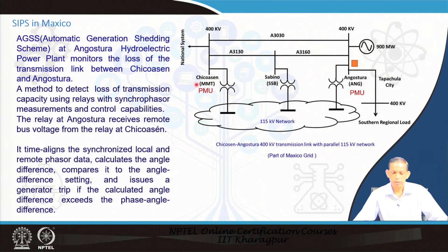So, what is being done here is that the double line outage produces a 14 degree angle between these two sides, and one line outage provides around 7 degrees of angle difference between both ends. So, a threshold of 10 degrees is selected between these two phasors, the angle between these two voltage phasors, the local one at the generating station side and the remote one. These two give us the angle difference delta, and if delta is greater than 10 degrees, then tripping of the selected generator is to be accomplished.